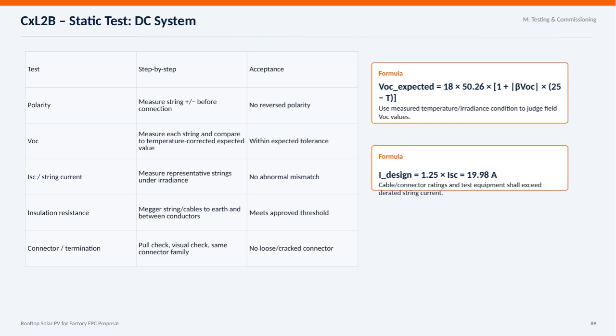The design current is calculated here as 1.25 times the ISC, which comes to just under 20 amps, and it's important that cable and connector ratings, as well as test equipment, exceed this derated current for reliable and safe operation. Overall, this thorough testing ensures our DC system is correctly installed and ready for commissioning.